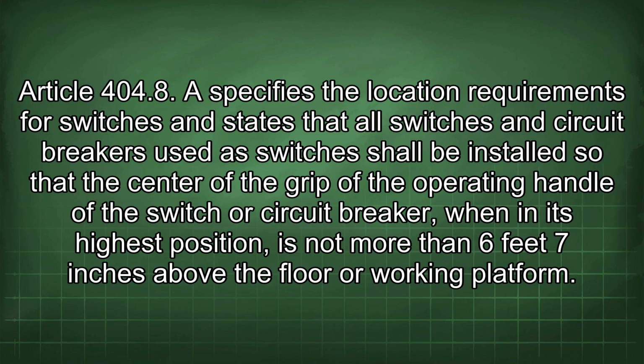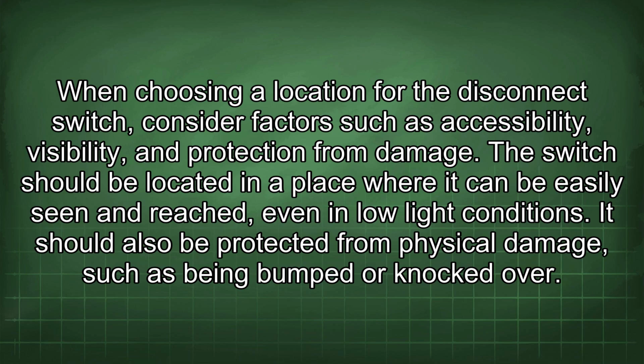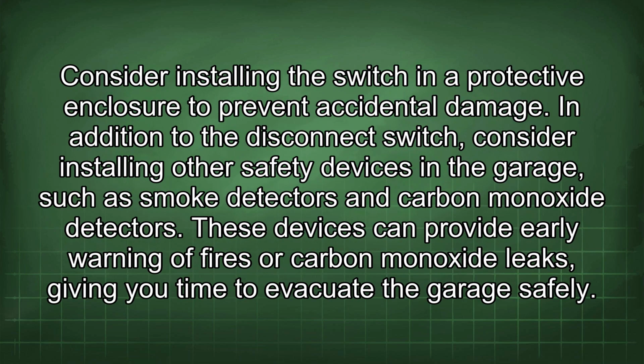Article 404.8 specifies the location requirements for switches and states that all switches and circuit breakers used as switches shall be installed so that the center of the grip of the operating handle of the switch or circuit breaker, when in its highest position, is not more than 6 feet 7 inches above the floor or working platform. When choosing a location for the disconnect switch, consider factors such as accessibility, visibility, and protection from damage. The switch should be located in a place where it can be easily seen and reached, even in low light conditions. It should also be protected from physical damage, such as being bumped or knocked over. Consider installing the switch in a protective enclosure to prevent accidental damage.